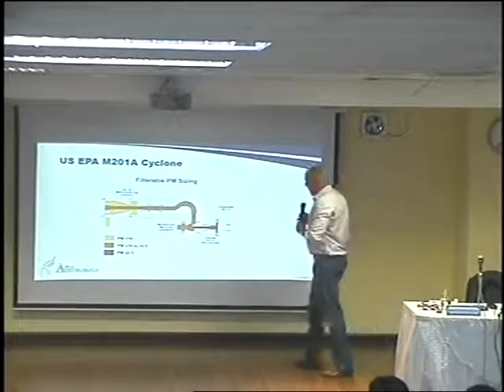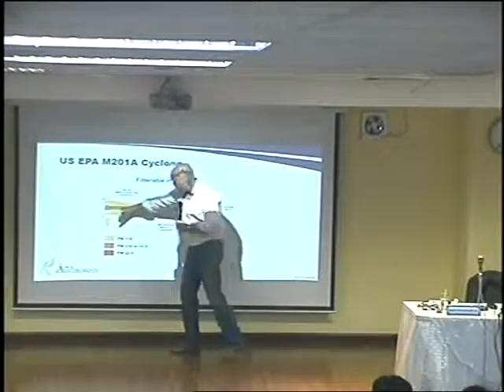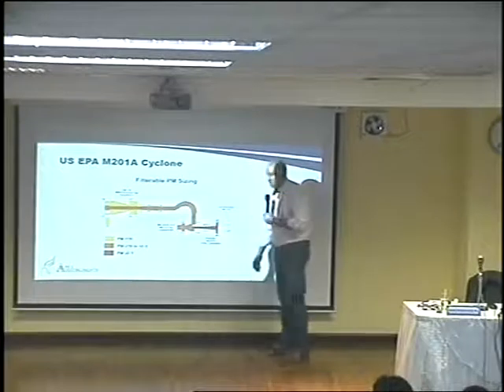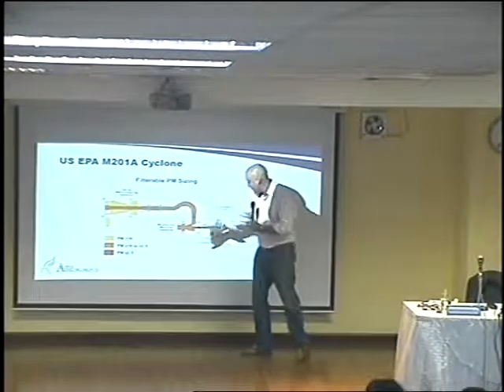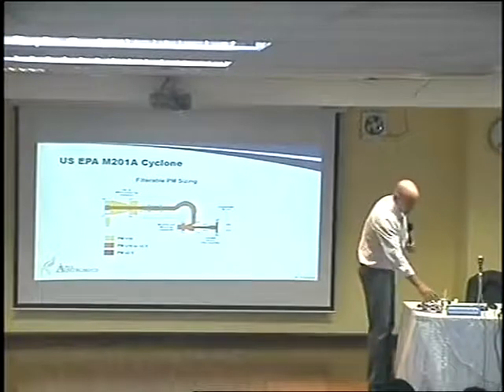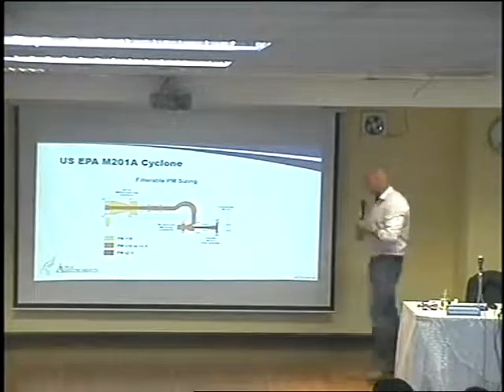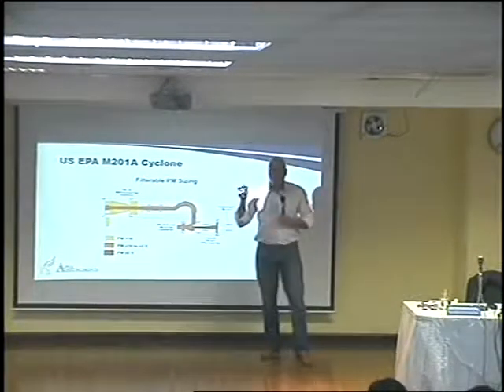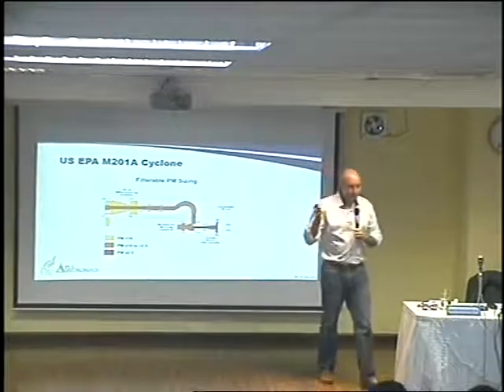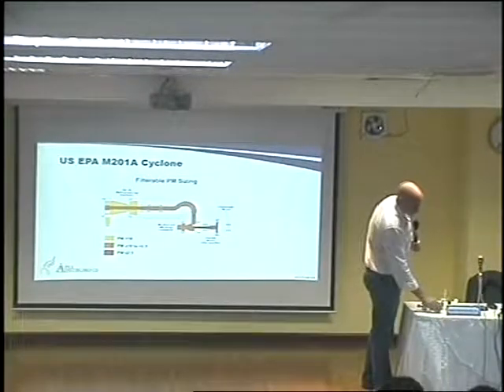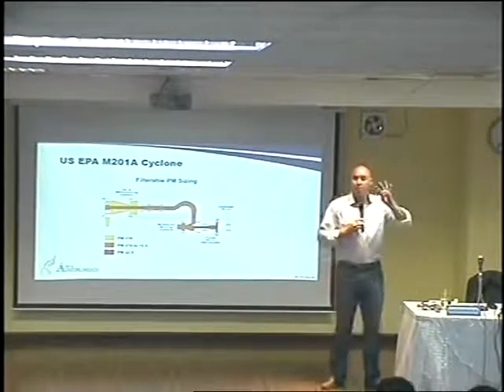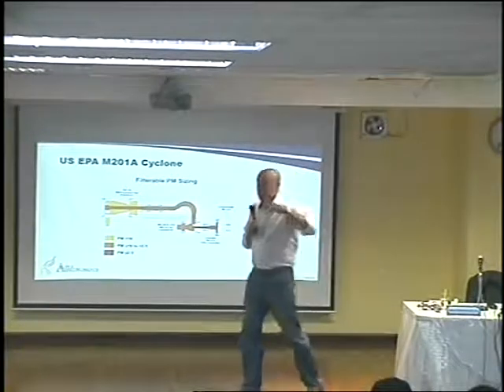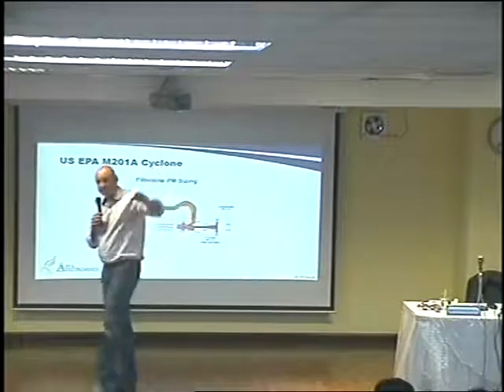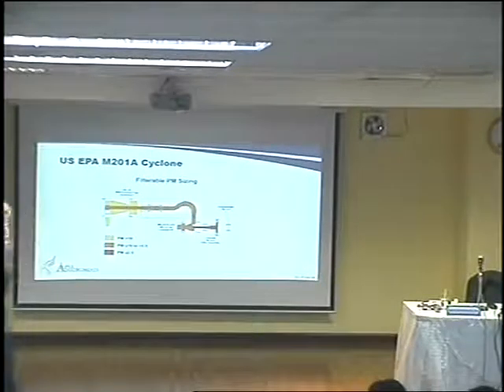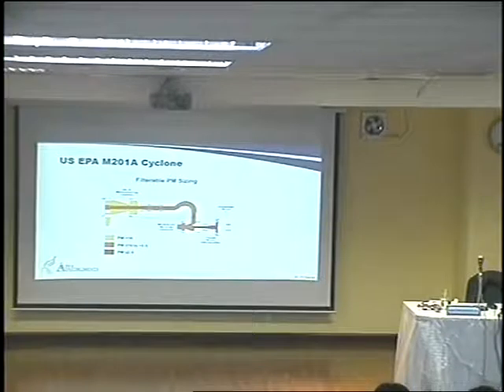And then finally, once you come down between the 10 and 2.5, the last stage here, in the filterable, this last filter is going to collect our sizes smaller than 2.5. So in theory, once you've finished sampling, you'll be able to report 3 numbers to your client or to the government: everything bigger than 10, everything between 10 and 2.5, and everything smaller than 2.5, okay?